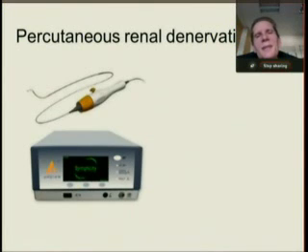This is the actual device. You can see the ablation catheter on the left-hand side in the upper portion. You have a handheld device where you can actually steer the distal tip. You can flex it in different directions. Then you see the console, which gives you feedback on the impedance and the drop in impedance while you're ablating.